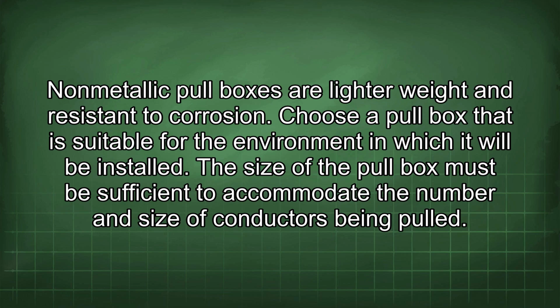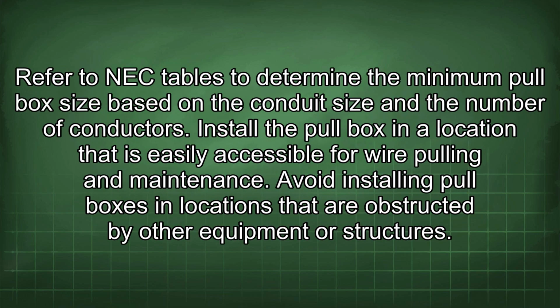The size of the pull box must be sufficient to accommodate the number and size of conductors being pulled. Refer to NEC tables to determine the minimum pull box size based on the conduit size and the number of conductors. Install the pull box in a location that is easily accessible for wire pulling and maintenance. Avoid installing pull boxes in locations that are obstructed by other equipment or structures.